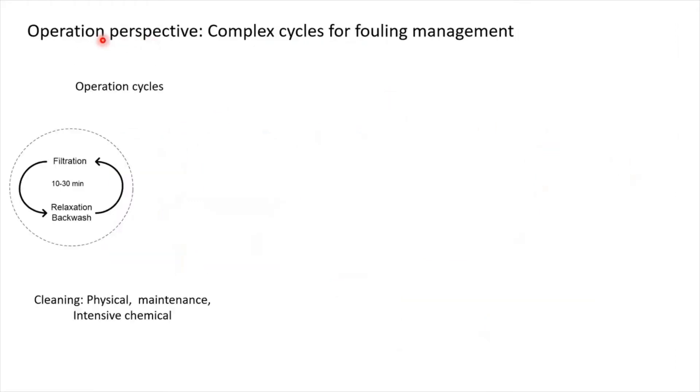In the operational perspective, fouling management results in a complex cycle of operation. As you can see from this illustration, you can develop a lot of cycles. First filtration with relaxation or backwashing. This is the cycle of short one within 10 to 30 minutes. Then we might implement some sort of maintenance chemical cleanings that can be done in one or two weeks with a low concentration of cleaning agents. And then from time to time, normally twice a year, depending on the performance of your system, you will probably need to do the intensive cleaning.